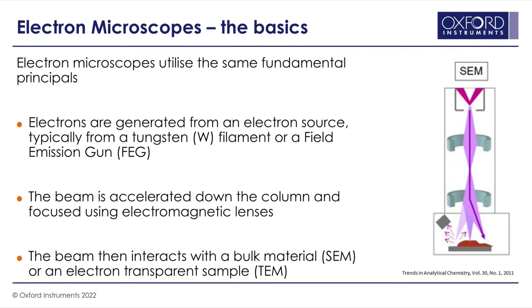Just as a quick recap: electron microscopes are very similar to light microscopes. In an SEM we are using an electron source instead of light, accelerating electrons from maybe a tungsten filament or a field emission gun. Those electrons are then accelerated down the column and focused using an electromagnetic lens rather than a glass lens. Eventually they interact with your sample. In an SEM it interacts with a bulk sample and we look at what signal gets bounced back, whereas in a TEM we are looking at electron transparent samples — looking at the electrons that pass through a sample and capturing any interactions that occur.